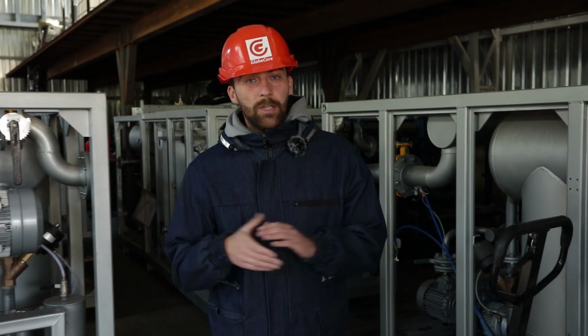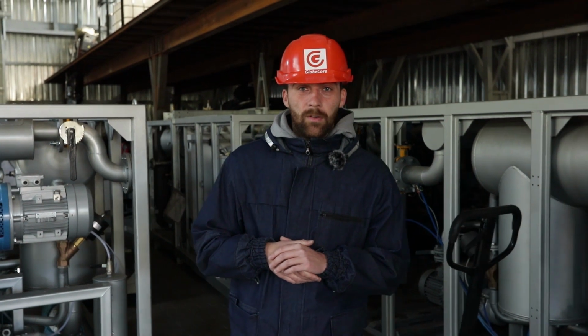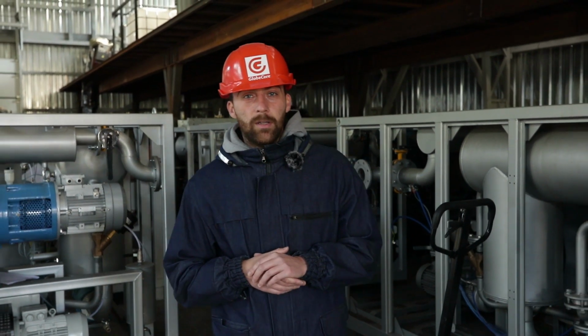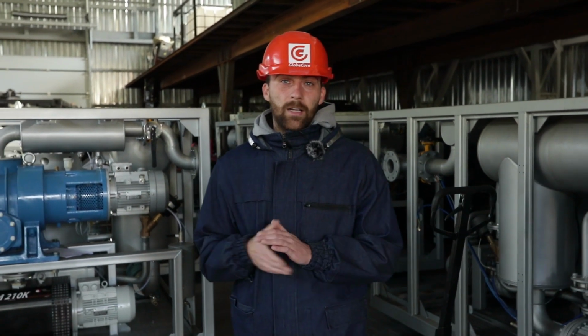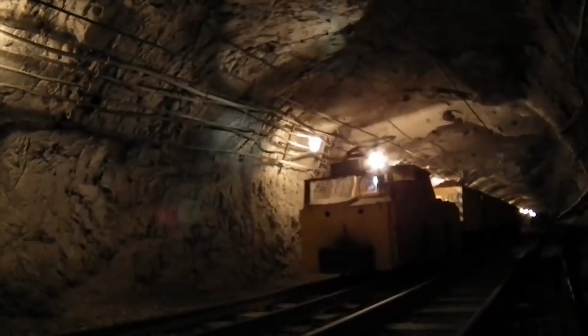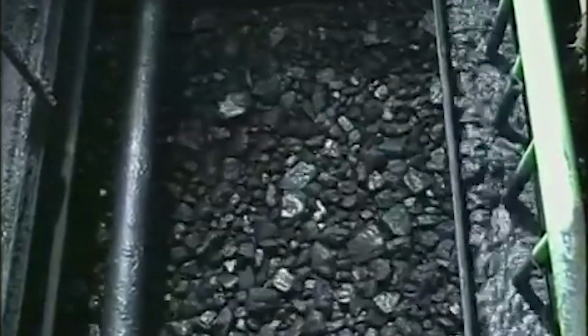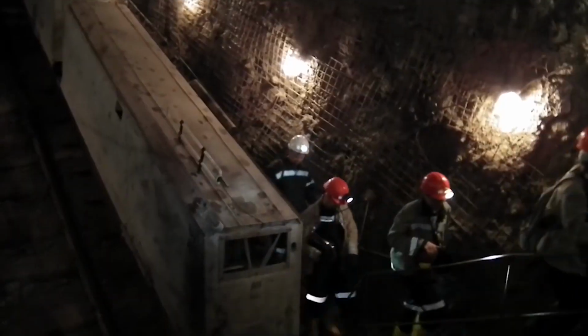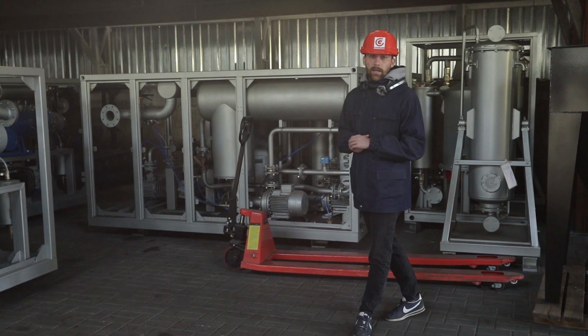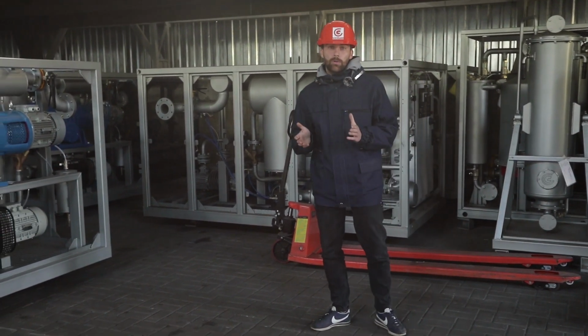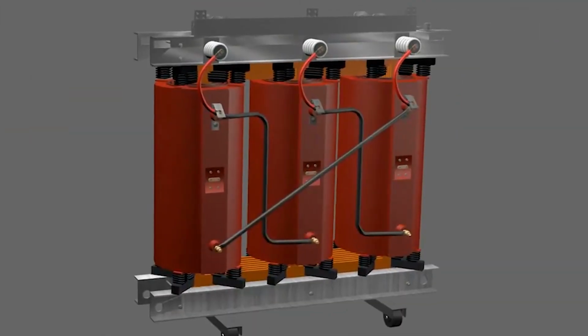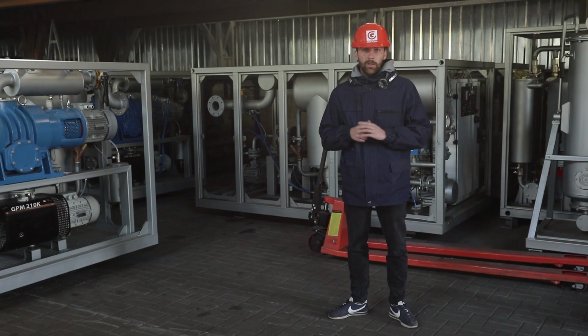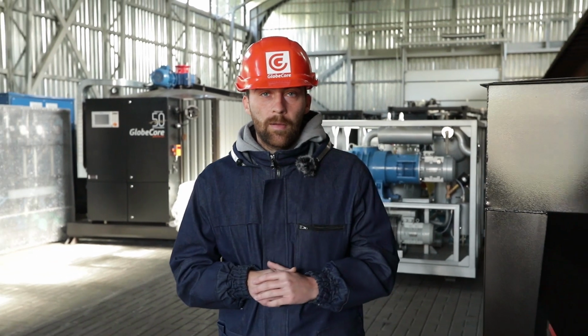Hello. Today, we will talk about special aspects of maintaining the transformers for electrical energy conversion when supplying power for subsurface mining works in mines. One of the main requirements for such transformers is the inability to inflame and to sustain combustion. Thus, flammable petroleum oils are not normally used for electrical insulation and heat removal in the conditions of mines. Preference is given to either dry-type transformers or transformers with fire-resistant dielectric liquids.